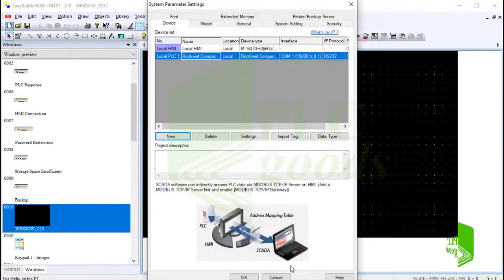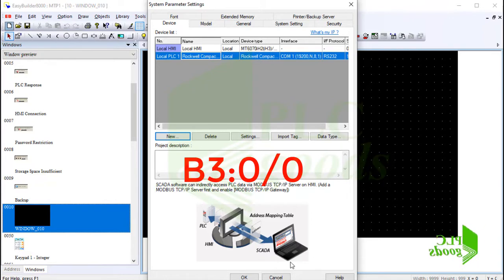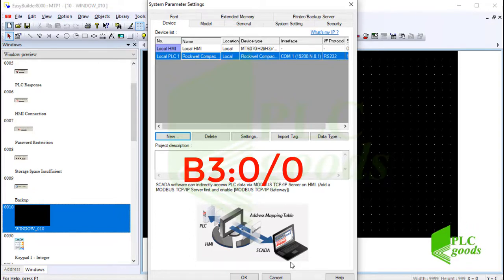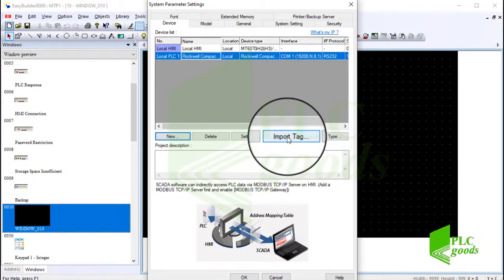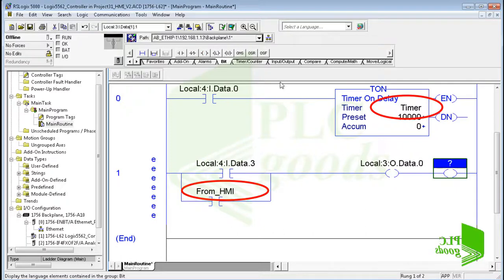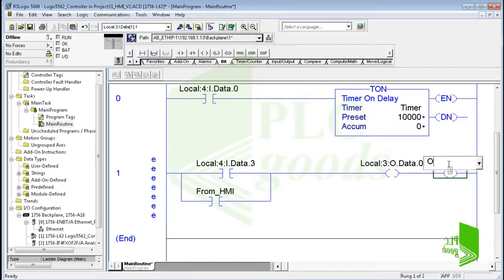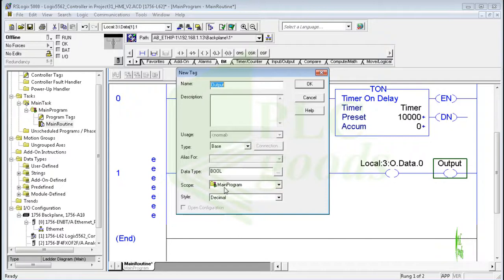Note that some PLC types like SLC 500 or MicroLogix 1500 use predefined addresses. For example, the first boolean memory address is B3:0/0. I can use this format to reference each PLC memory address inside the HMI screen. However, I defined and use some tags inside my PLC program which don't follow any format, so I need to import them into the HMI. Inside the PLC program these tags were defined before. Now let me define another tag — the state of this tag is equal to this digital output, so I can use this tag in my HMI screen to display the output state.